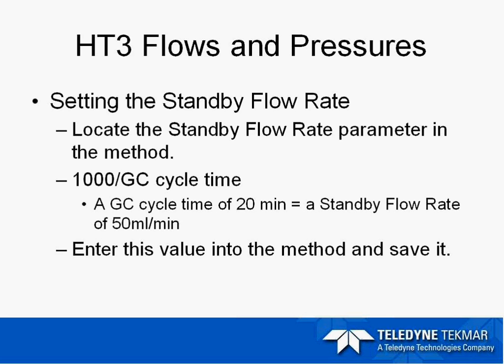Typically, if you're using the same gas tank for your GC and your HT3, set the tank pressure at 80 PSI. Standby flow is very easily set in the method of the HT3 and can be changed depending on the HT3 and GC method run. If you have multiple methods based on different operating conditions, you can change the standby flow rate in the method — you don't have to worry about measuring the gas flow at the needle with gauges like you do on the 7000. Just locate the parameter in the method, change it, and save it. The standby flow rate should be 1000 divided by our GC cycle time to ensure we flush the sample loop between each sample and prevent carryover.